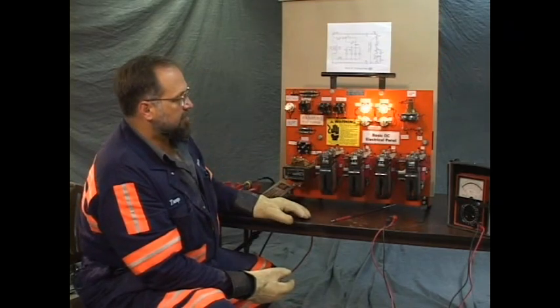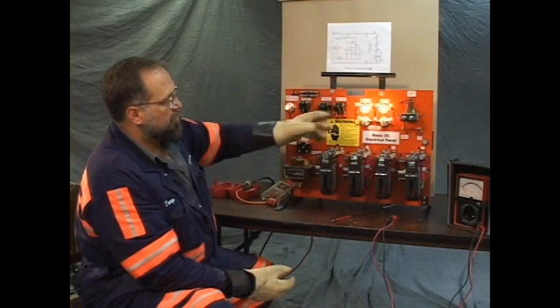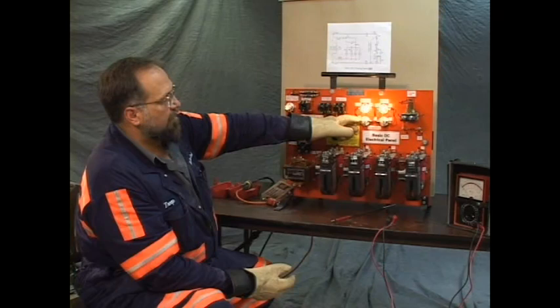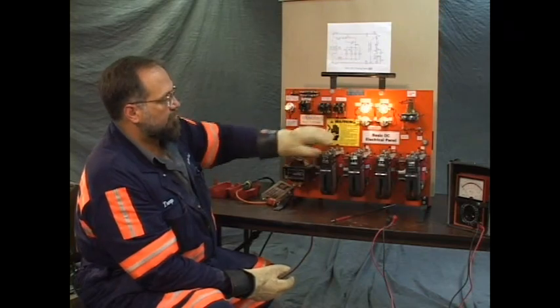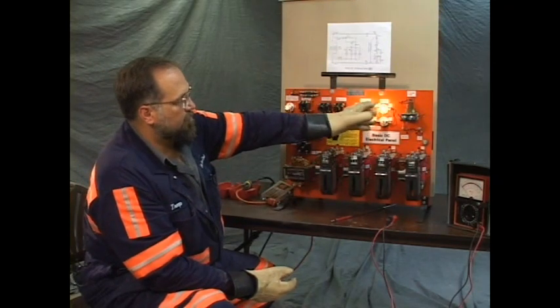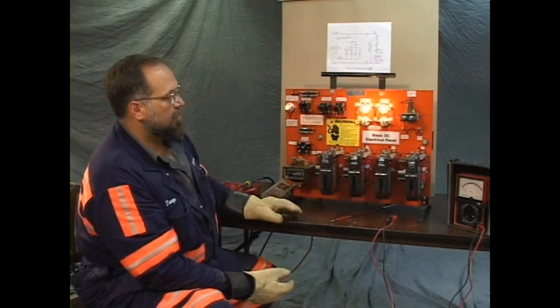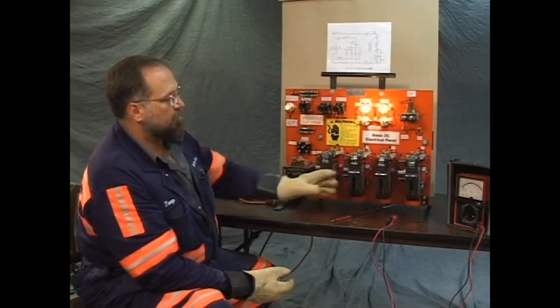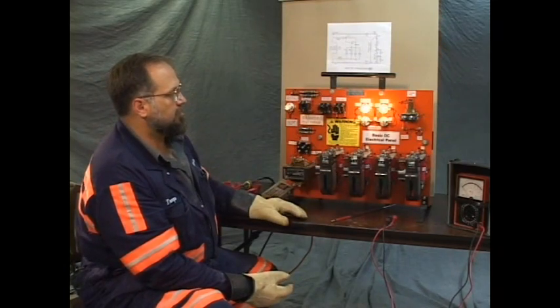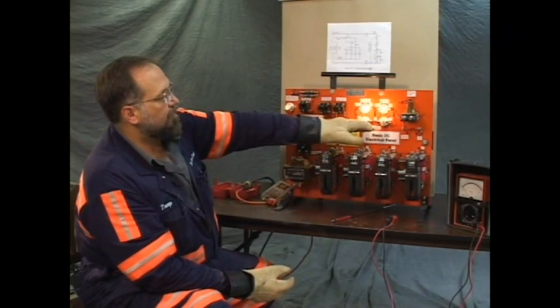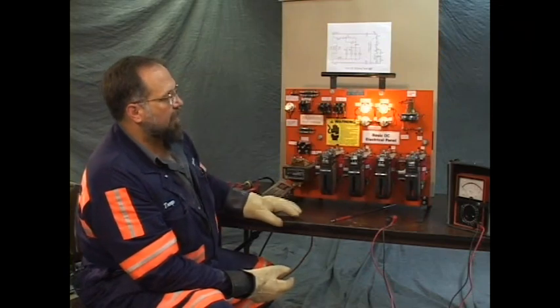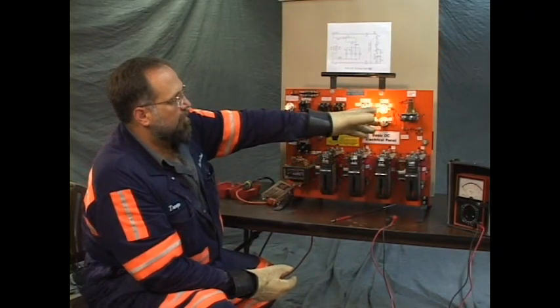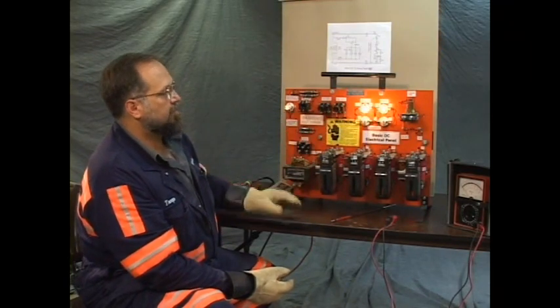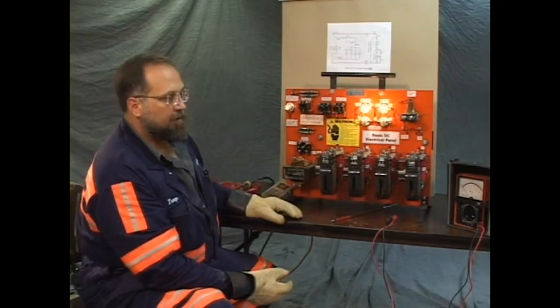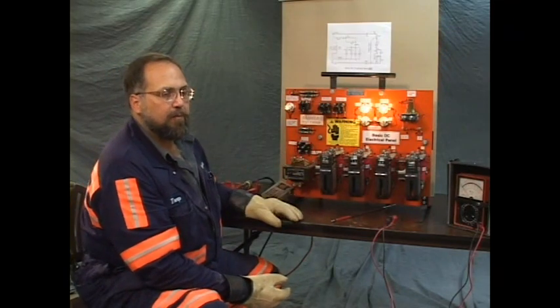First second passes, 1A closes. This light on the bottom left will go out. These other 2 will get brighter. After another 1 second interval, 2A contactor closes. When it closes, the bottom right light goes out and the armature gets very bright, same as the shunt field. That would be top speed on the motor.